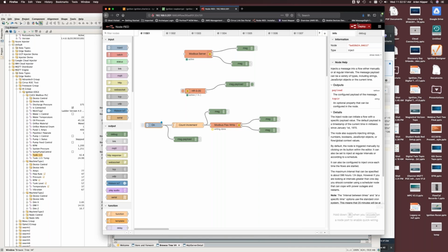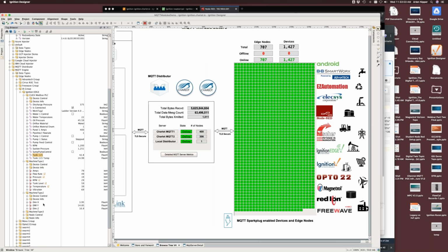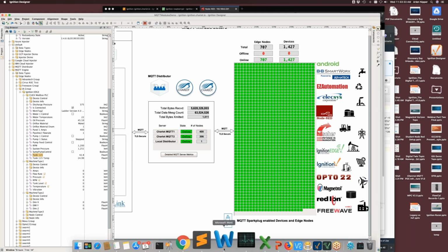Okay, so we're going to turn off our IO. And you'll notice when I did that, all these tags went stale. They're all red. What that resulted in is we published a message up to Kinesis that said that all those tags went stale. So that's how we have state. Even though we're decoupled, and we may only be publishing once every 2 seconds or once every 10 seconds, we know exactly if that process variable went offline, and we know the timestamp of when it did. That's one of the enablers of being able to publish data on exception, but still know that you've got the truth of your data.